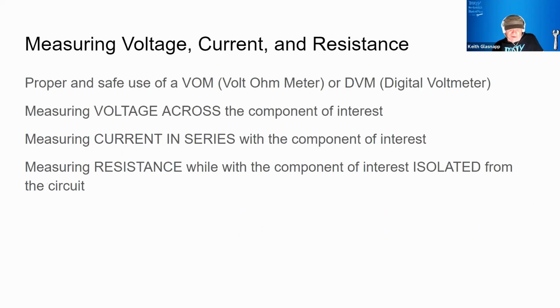As an aside, the way we found the problem was by putting a voltmeter across the battery and finding it was always 12 volts, but when we put the voltmeter across one of the motor controllers and ran the motor, the voltage dropped to maybe 7 or 6 or 5 volts. So we knew there was a resistance problem between the battery and the motor, because the motor was running at 5 volts while the battery was at 12.